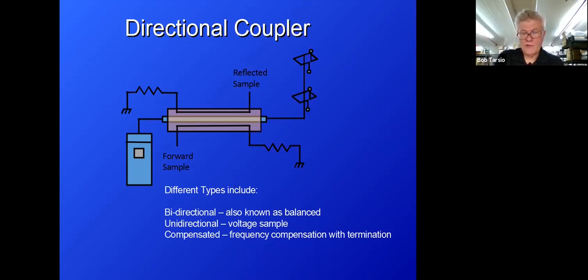Then there's the unidirectional or voltage sample. I'll talk a little bit about that in just a second. And then the compensated or frequency compensated with termination type coupler. This particular coupler here on this meter, to do 80 to 1,000, you have to do a termination, and you have to have a network in there that's going to flatten the response. The bidirectional coupler, basically because of the capacitive nature of it, has a 6 dB per octave rise in response. So you have to sweep it and know the band of interest that you want to use it for, but it offers the best directivity, and I'm going to talk about that in just a minute.